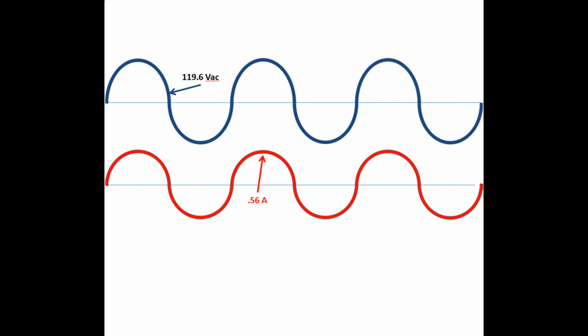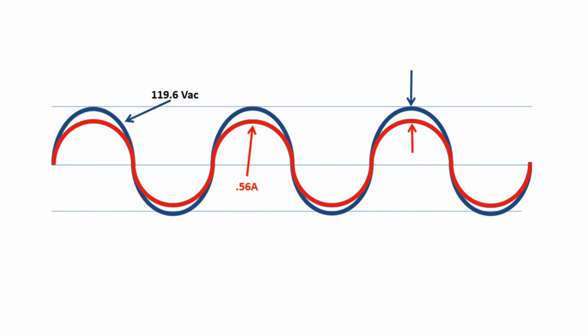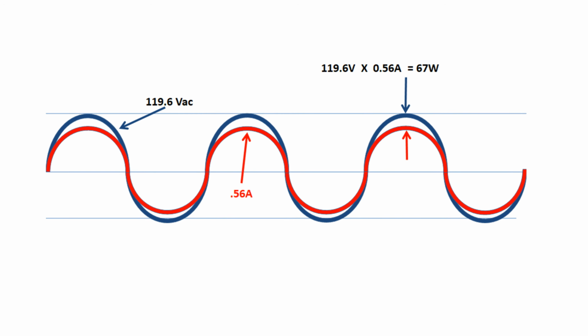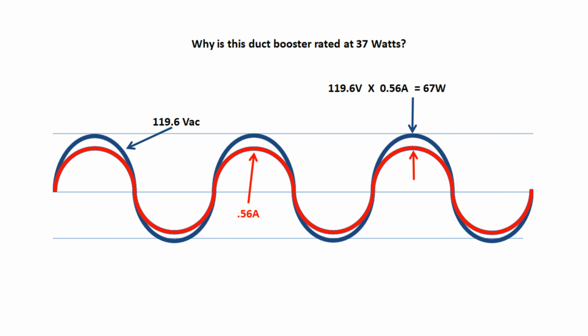These are drawing representations of our AC voltage and amperage sine waves. Notice they appear to be in phase with each other. It appears more obvious they're in phase when we superimpose them on the same axis. And if we multiply our measured volts times amps, we get 67 watts. So why is the duct booster rated at 37 watts?